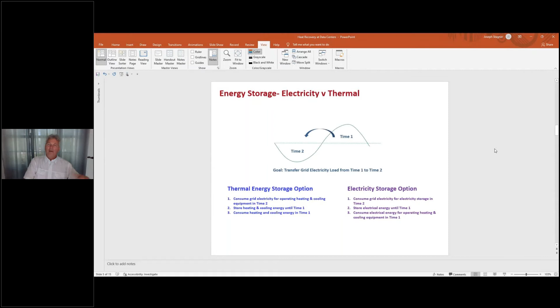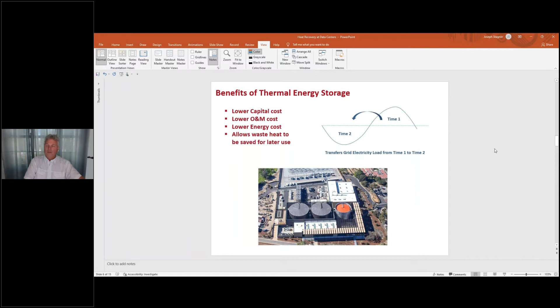That's why Stanford has a great deal of thermal storage for shifting that load. It lowers our peak electrical demand, increases our load factor on the grid, and is a lot cheaper than buying more chillers. It does all kinds of good things and could do it for a data center too, if you have a sinusoidal heat generation pattern.